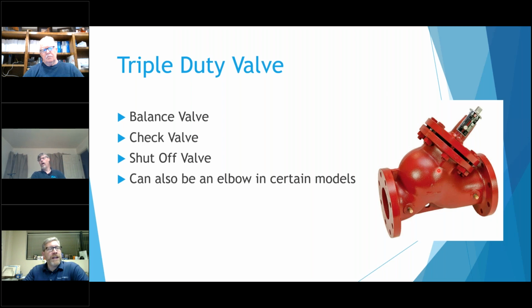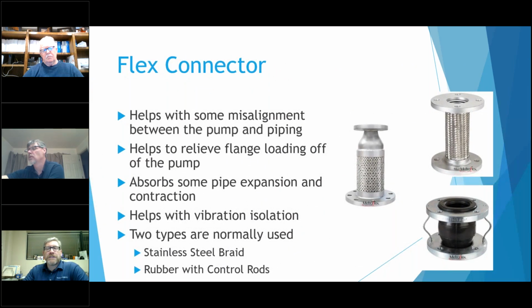There's also an angle version of this that you can use as an elbow as well. Flex connectors are another item that we see on the pumps quite a bit. The big thing that I like to see them on there for is that it alleviates a lot of the pipe strain that might be on a pump. Like I said, I've seen a lot of pumps where the pipe is coming in and there's no support or virtually no support, or it's kind of jammed in there.